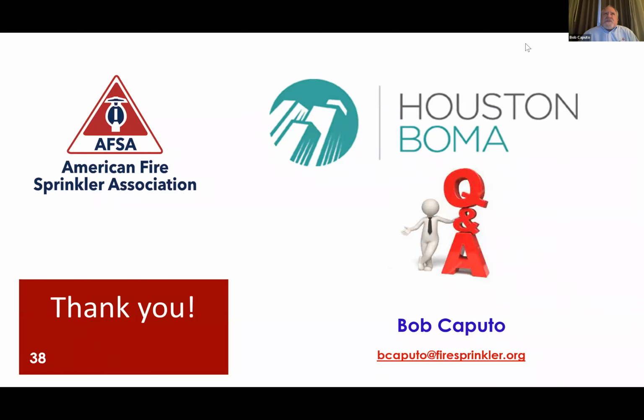So when you've got vessels or containers, which could be as small as pints or as large as 55-gallon drums versus vessels that are pretty good size that are inside or outside of buildings with flammable combustible liquids, the code requires us to take the largest container plus 30, 60, or 90 minutes of water from the fire sprinkler system and have secondary containment. So I need to dish the floor or have a container subterranean so that all drains fill that. So the fire, we want to contain all of that hazardous material plus the water that's now contaminated. And after the fire is out, then we want somebody to come along and take that hazardous material away from the site. In some cases, instead of water, we're going to attack that fire with foam, aqueous film forming foam, or AFFF.